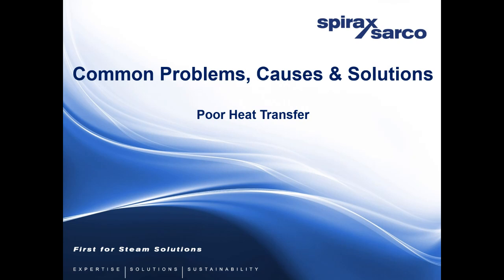On the high end of that as well, we also offer a system called Strata, which is remote steam trap monitoring and system monitoring. If you have a meter, be it for fuel, makeup water, effluent, steam, anything, we can digitize that, so you can see it on your smartphone, on your HMI in an office, anywhere on site. By monitoring those and being able to tell the inefficiencies in your returns, how much you're putting in compared to how much you're getting out, you can also have a good indication of any losses in your system. Strata itself, the licensing is relatively cheap. The expensive part is the meters. And if you've got existing meters there, that mitigates some of the cost too.